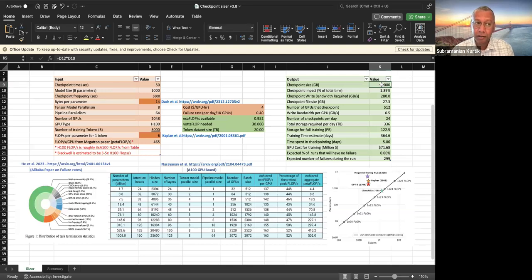So this has resulted in a lot of interesting strategies people are looking at, right? The Blackwells, for example, you cannot do this in air-cooled racks. When you go over 50 kilowatts, you're going to go to liquid cooling at that point. In fact, 120 kilowatt racks that are commercially out there are all liquid cooled, okay?